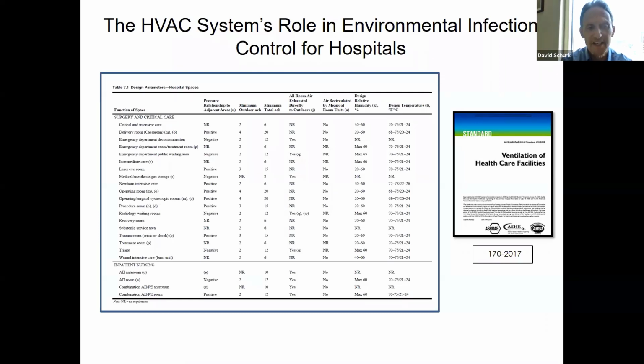Based on what a given space is assigned to accomplish, the standard gives us information on the pressure relationships of that space to another—whether positive or negative, whether it's trying to fight infection entering the space, or ensuring airflow pressurization is outward to protect individuals within that environment. It also covers the amount of outside air required for ventilation and the number of air changes required in that space, in terms of actually moving the air through the HVAC system.